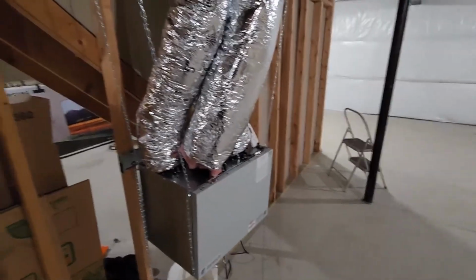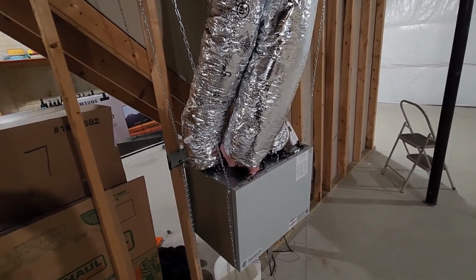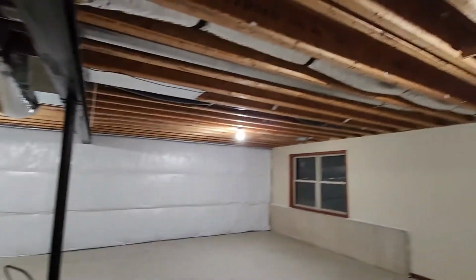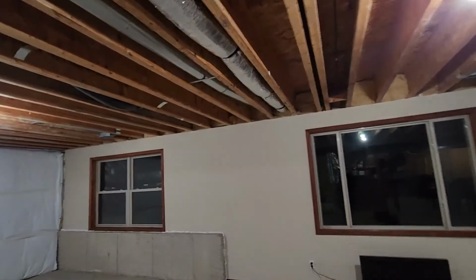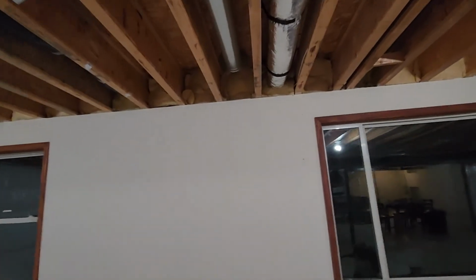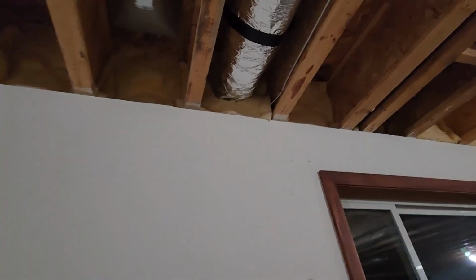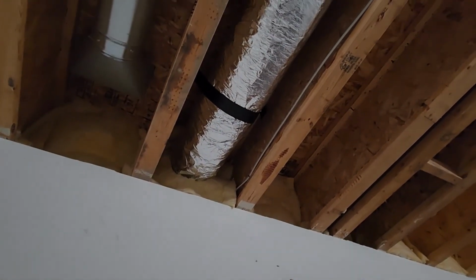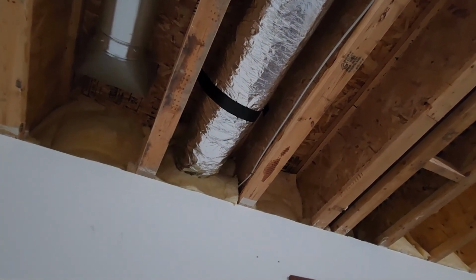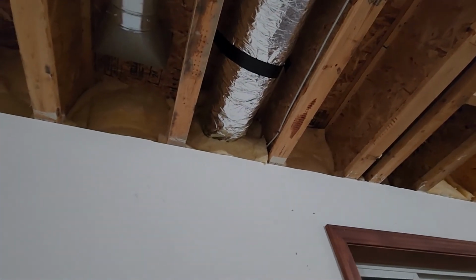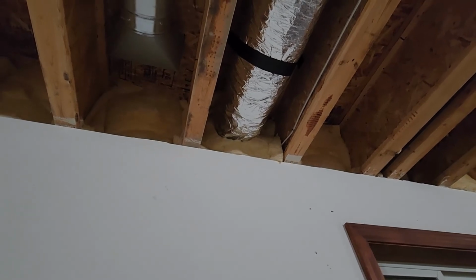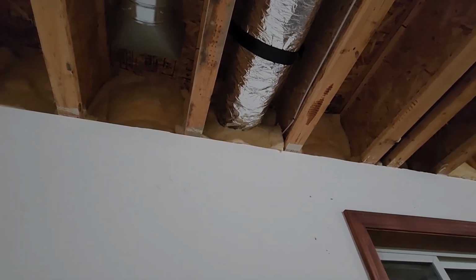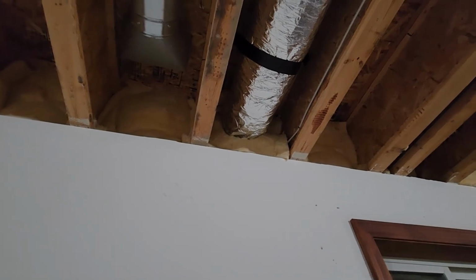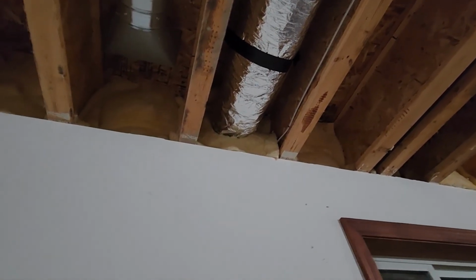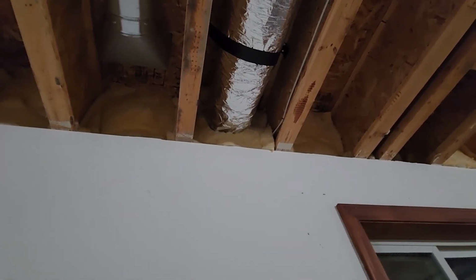I'll go ahead and show you guys the quick. I also bought Fantech 5-inch connections that we can make with the outside wall, and they've got sheet metal that runs about 18 inches into that flex duct, which is nice. And then I sealed it up. I drilled 6-inch holes through the plywood with a 6-inch hole saw, because by the time you have a 5-inch duct and then the insulation of a flex duct, you're almost at 6 inches in diameter.